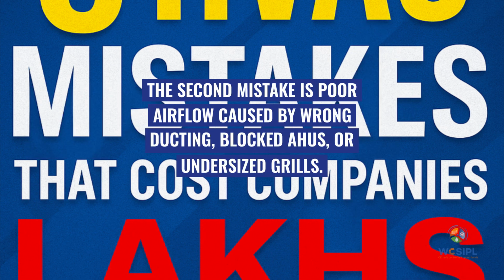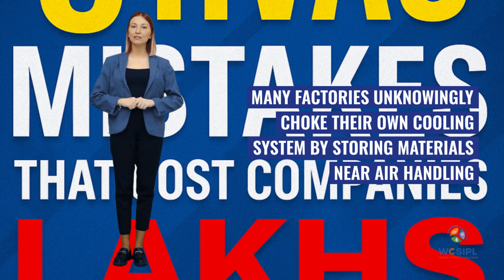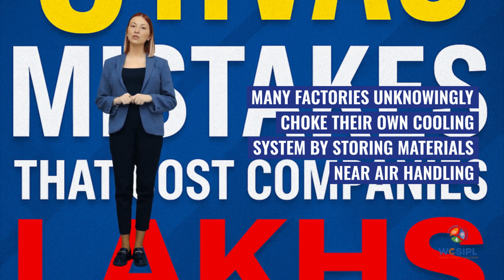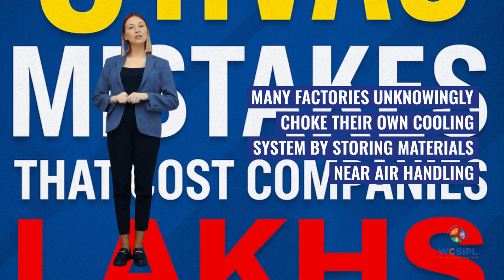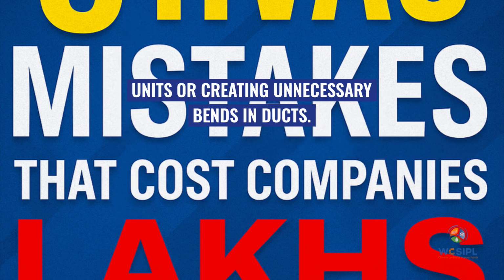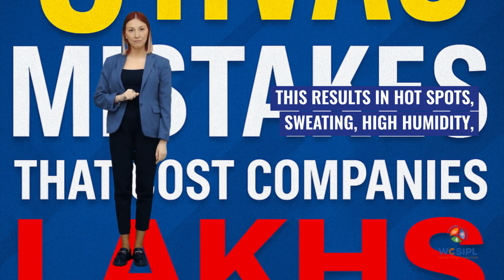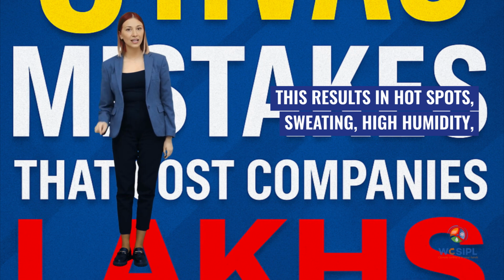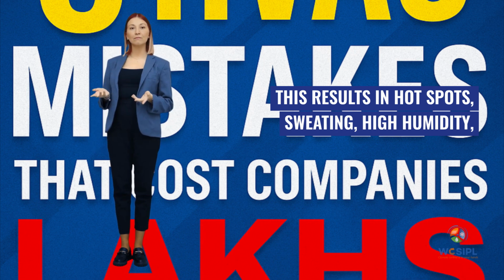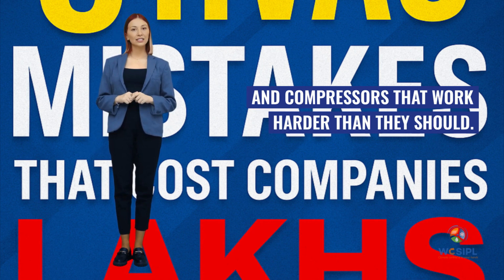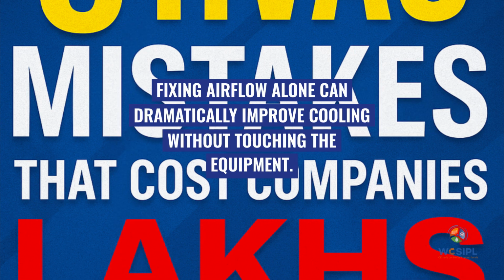The second mistake is poor airflow caused by wrong ducting, blocked AHUs, or undersized grills. Many factories unknowingly choke their own cooling system by storing materials near air handling units or creating unnecessary bends in ducts. This results in hot spots, sweating, high humidity, and compressors that work harder than they should. Fixing airflow alone can dramatically improve cooling without touching the equipment.